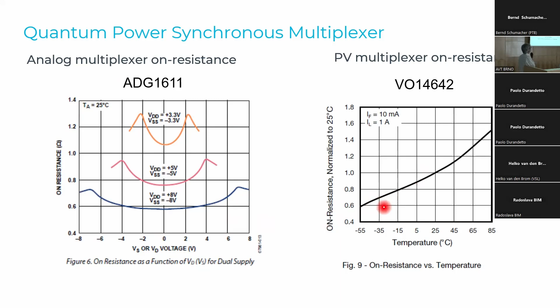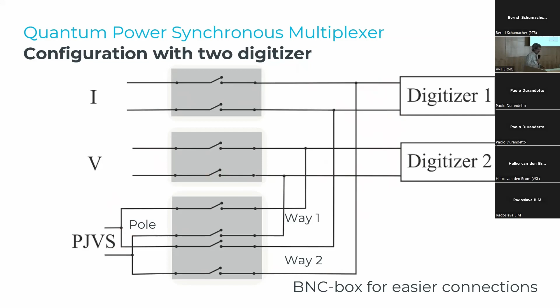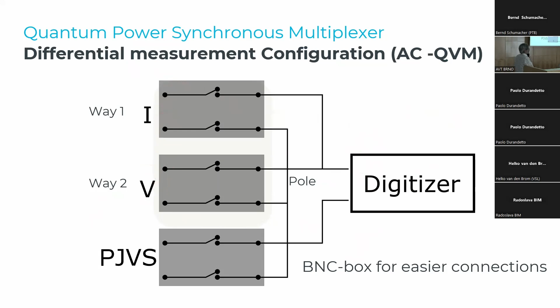In the connection diagrams, we can use 3 signals: current, voltage, and PJVS, and 1 digitizer. This is also part of the design considerations. Or you can use 2 digitizers, feeding current into one digitizer and voltage into another, but the PCBA is used to calibrate them to each other. Also, it's possible to use differential sampling. This is connected as a differential voltmeter, the PJVS together with the digitizer, so you select current or voltage.